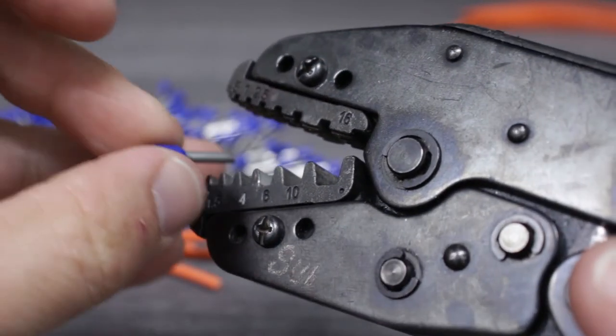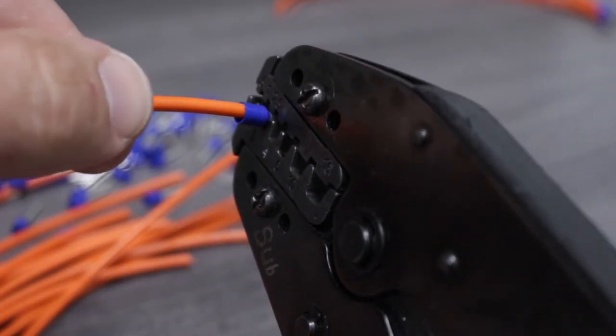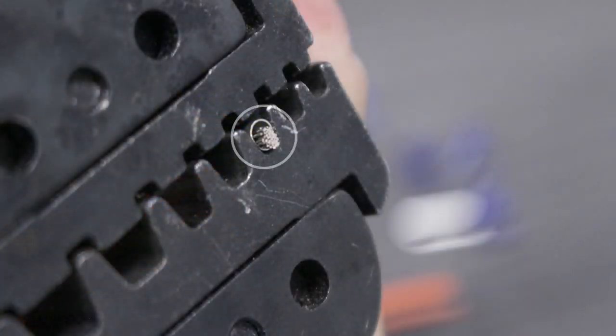We'll place the correctly sized ferrule into the proper crimp nest of our specialty tool. Now, we'll insert the wire making sure that the insulation of the wire butts up to the barrel of the wire ferrule and that the conductors end at the tip of the ferrule.